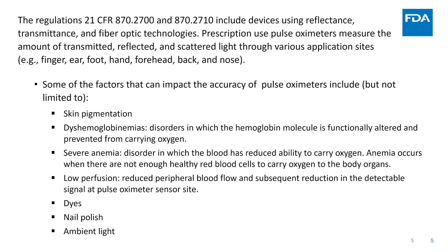In addition, there are other patient factors that may raise challenges regarding device accuracy and signal quality, like the ratio of oxygenated and deoxygenated hemoglobin, which does not include consideration for other types of hemoglobin. Therefore, disorders of the hemoglobin molecule or anemia may cause a reduction in pulse oximeter accuracy, in addition to other factors like intravascular dyes, tattoos, nail polish, and ambient light. These may interfere with the sensor and contribute to lower accuracy.